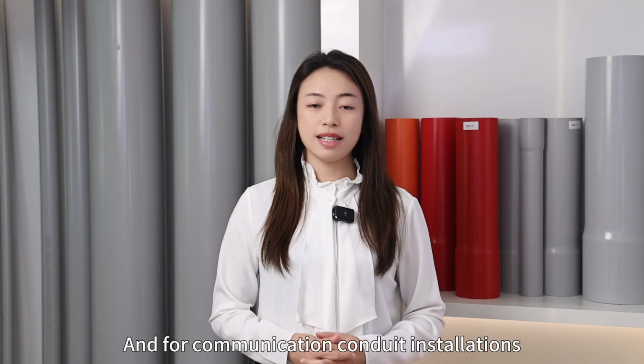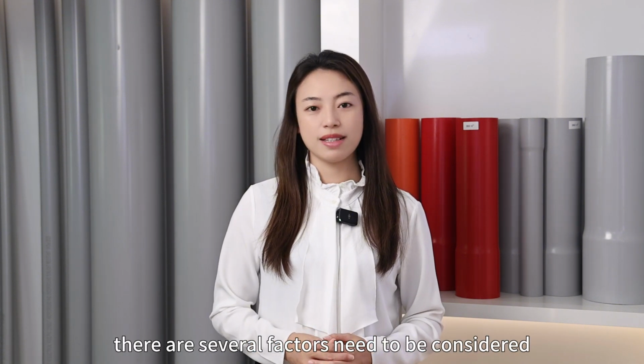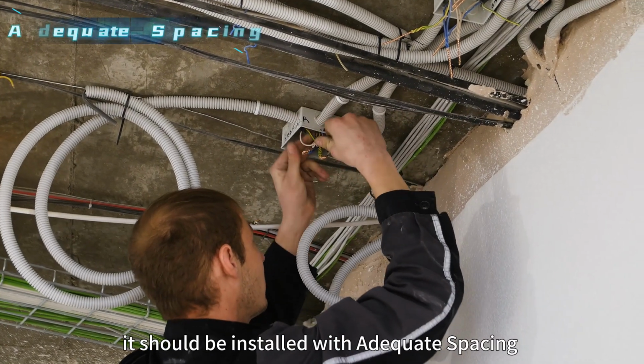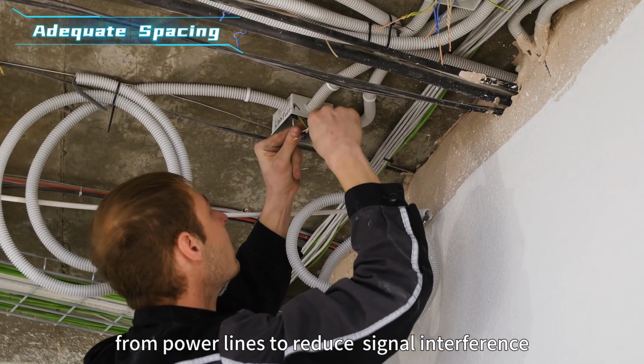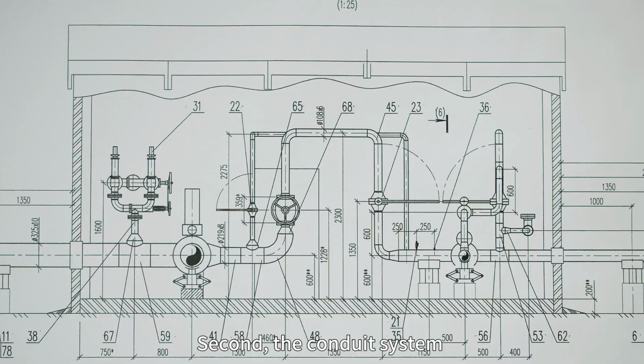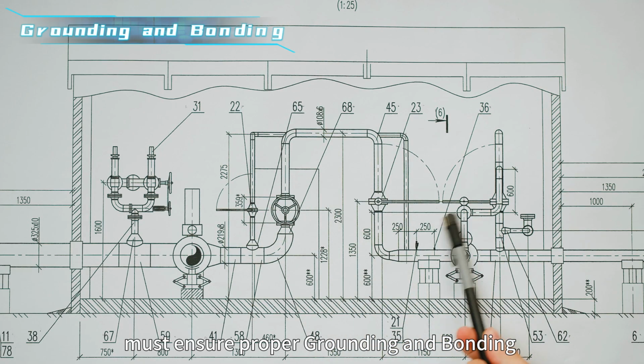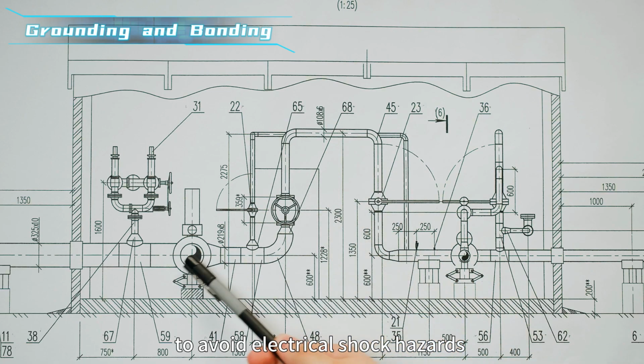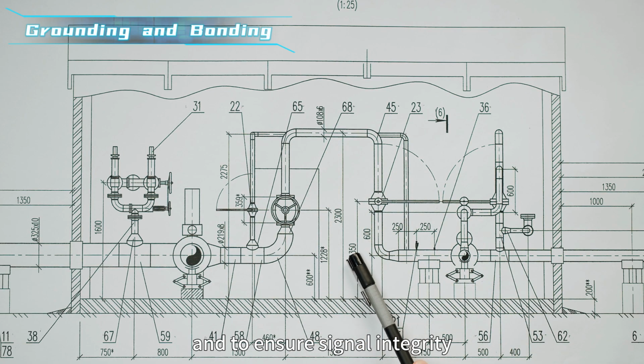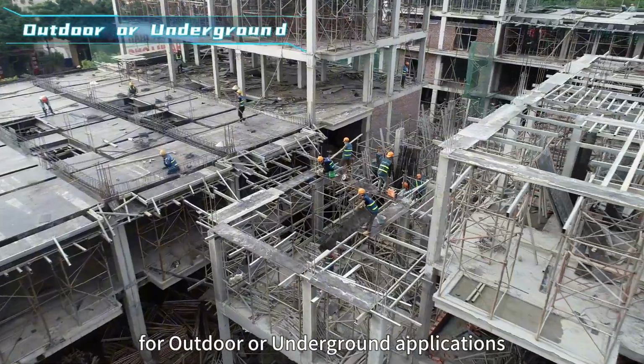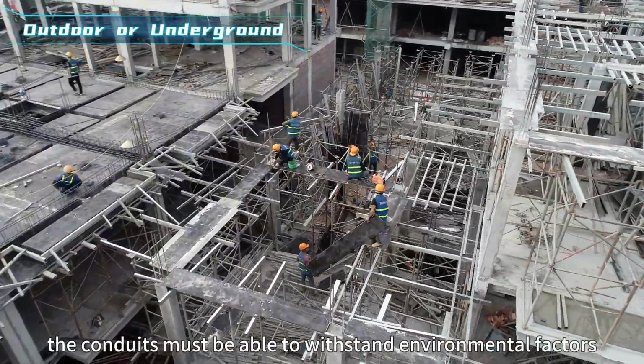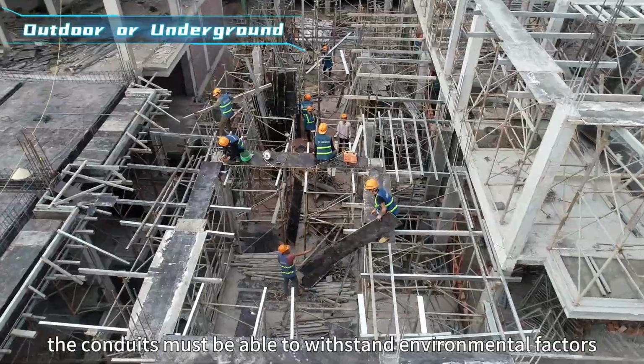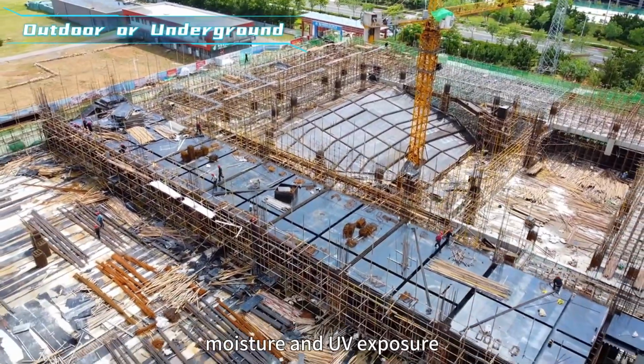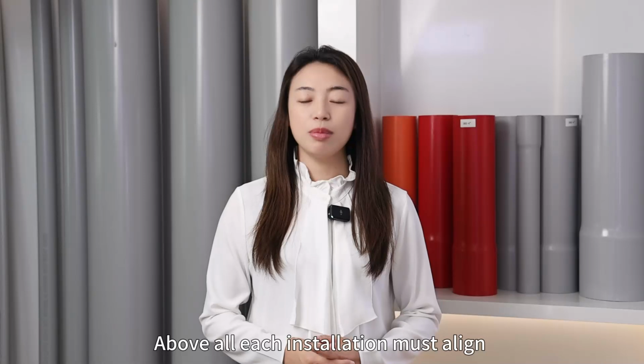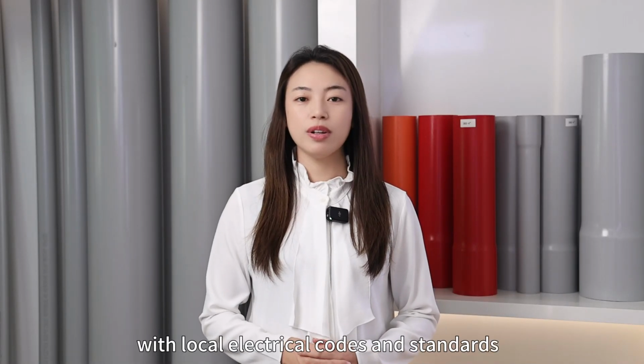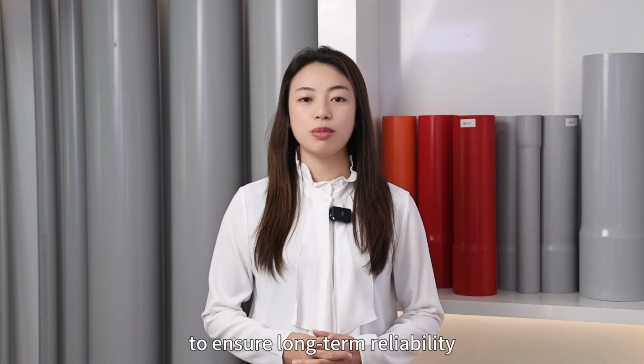And for communication conduit installations, there are several factors that need to be considered. First, it should be installed with adequate spacing from power lines to reduce signal interference. Second, the conduit system must ensure proper grounding and bonding to avoid electrical shock hazards and to ensure signal integrity. And third, for outdoor and underground applications, the conduits must be able to withstand environmental factors of temperature fluctuations, moisture, and UV exposure. Above all, each installation must align with local electrical codes and standards to ensure long-term reliability.